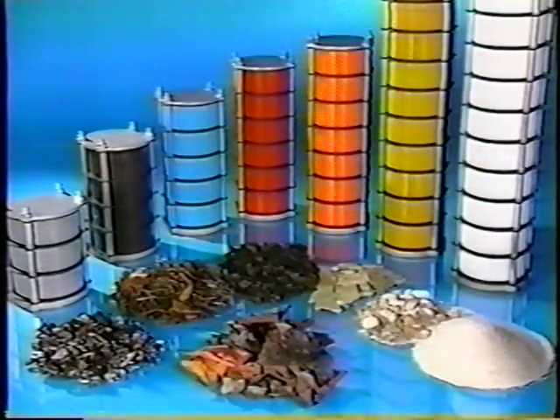When a preset level of filter fouling is reached, the backwash process is initiated. Reverse flow releases the pressure on the lips of the filter elements, causing them to spring back, enabling even those particles that have become firmly lodged to be removed. In the filtration process, even at minimal flow, the lips of the filter element return to their original position along the spacers to form a filter gap once again. The development of the active filter elements enables Taprogge to meet all demands for fine filtration. Through this finely graded filter range from 50 to 1000 microns, all types of debris can be combated effectively.